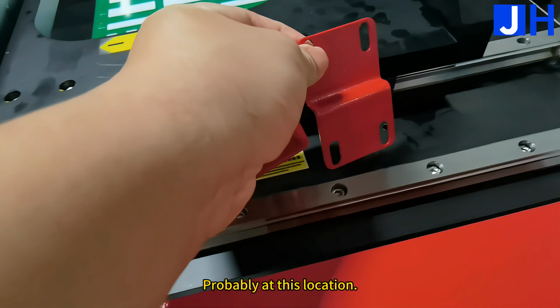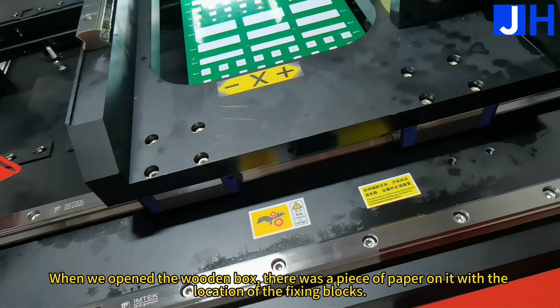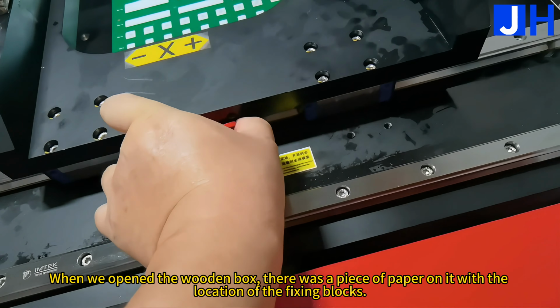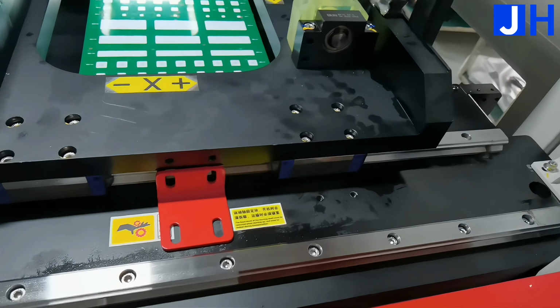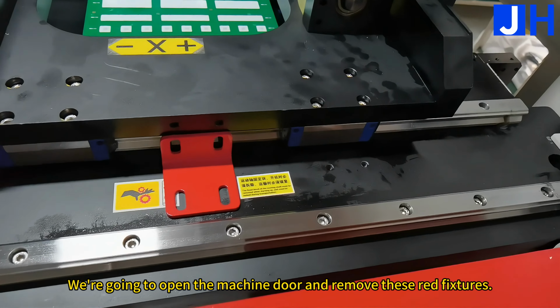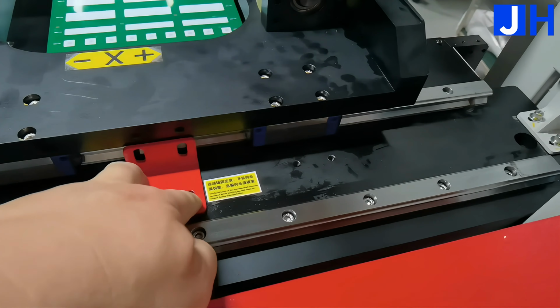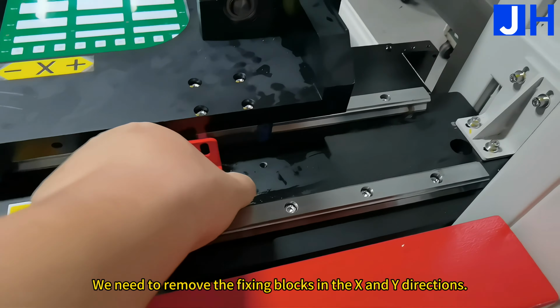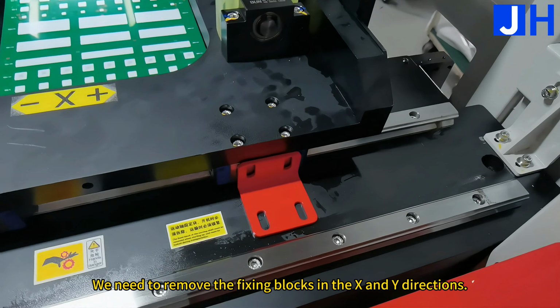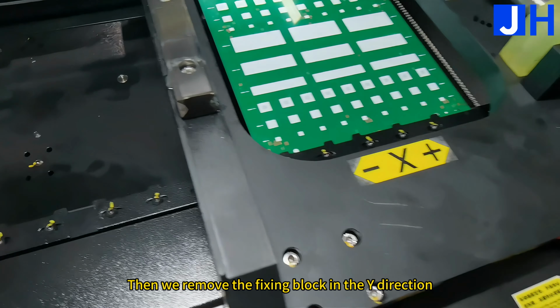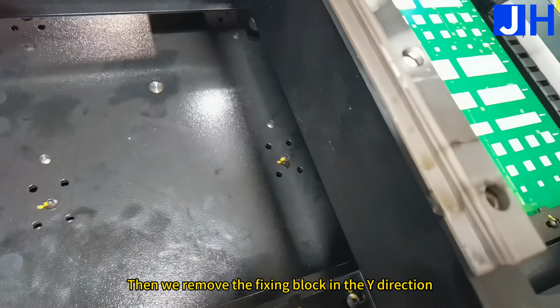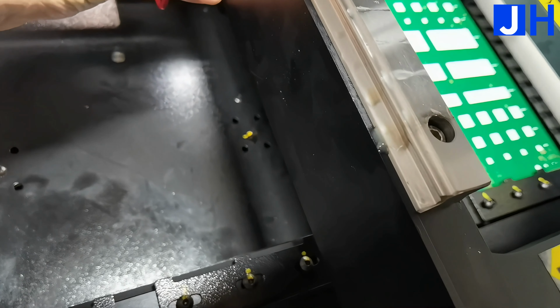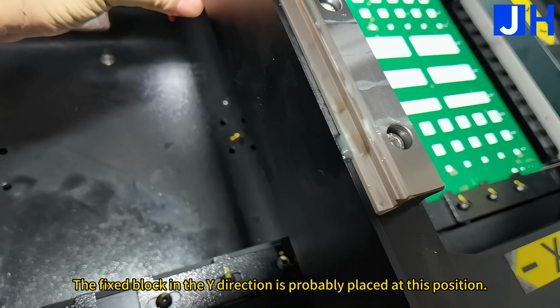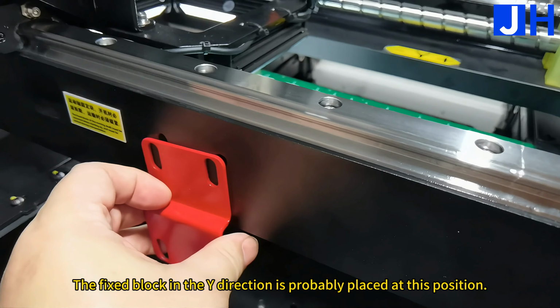It is probably at this location. When we opened the wooden box, there was a piece of paper on it showing the location of the fixing blocks. We are going to open the machine door and remove these red fixtures. We need to remove the fixing blocks in the X and Y directions. Then we remove the fixing block in the Y direction. The fixed block in the Y direction is probably placed at this position.